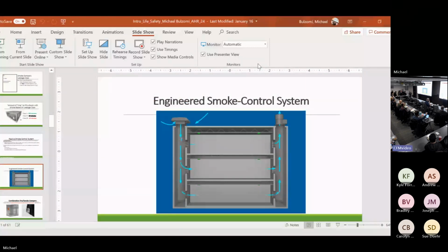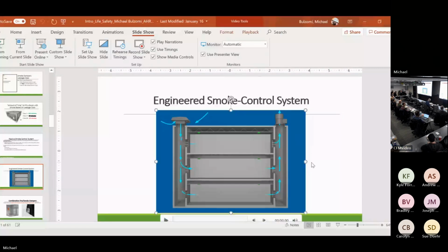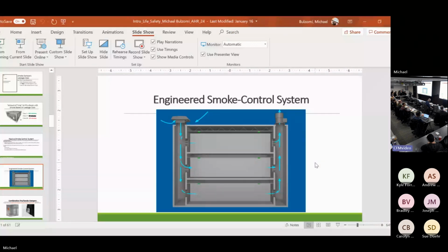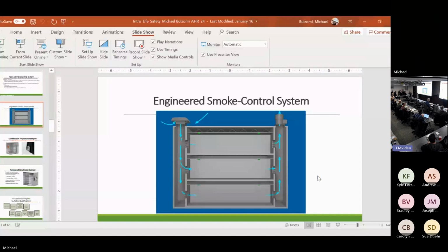Here's a typical diagram of an engineered smoke control system. No, that didn't work. Well, I'll just manually do it for you. So basically, you're going to have your supply air, supply hood. You're going to come in, maybe your return air. Fire is going to break out on the second floor. I'm going to close my dampers on the return side. So I'm going to positively pressurize the first and third floor. I'm going to close the supply side. I'm going to negatively pressurize on the second floor, and I'm going to exhaust my smoke out.